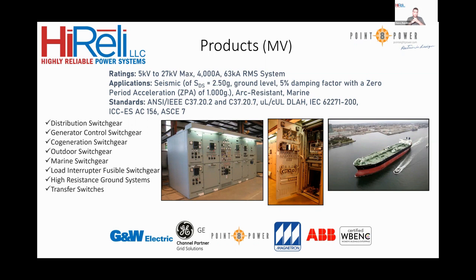63 kA interrupting. Here again, the first picture shows a medium voltage marine application of metal clad gear, and it shows you a two-high configuration, meaning there's a second breaker above the first bottom breaker, so that's a two-high construction.